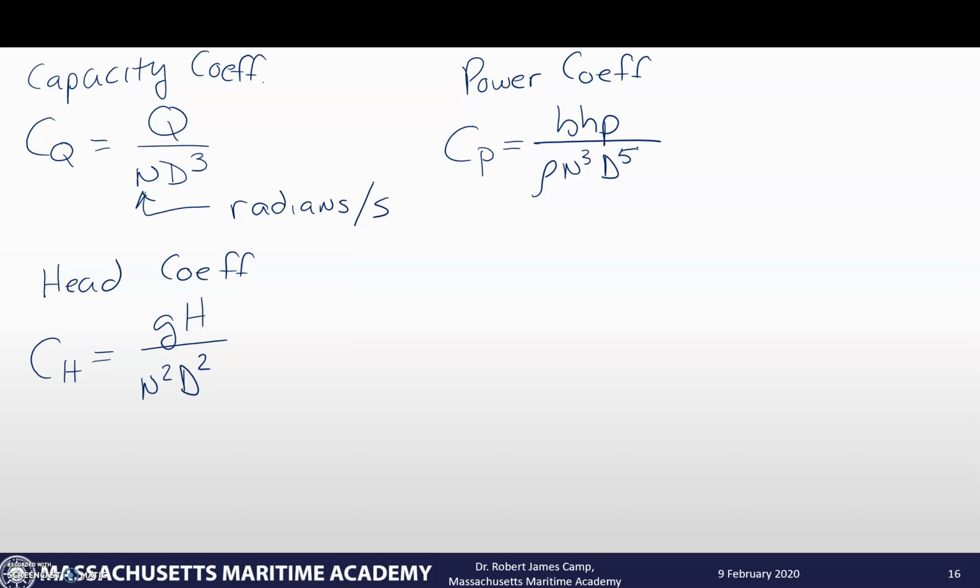Now this is another one where a pump is similar to itself, which makes a lot of sense for you to be able to do some kind of analysis on, because if you have a pump, and most pump curves are tagged to water, let's say you wanted to move maple syrup, which is quite a bit thicker than water. Well, how do you calculate out how that pump's going to work in that new environment? Well, that's where you change the density of this, and then you match it back to what the water should be.